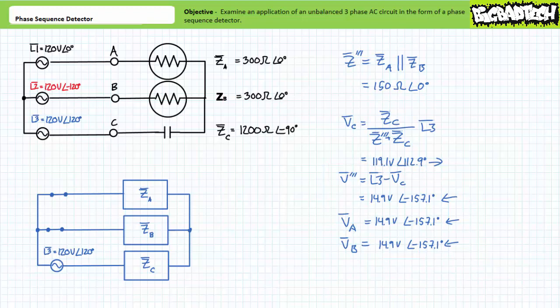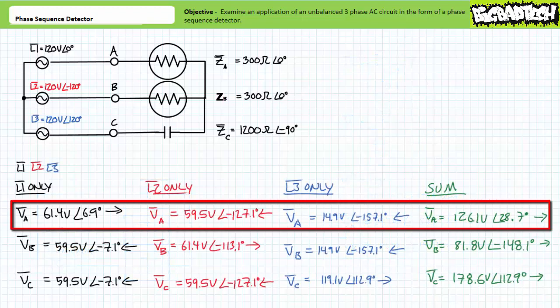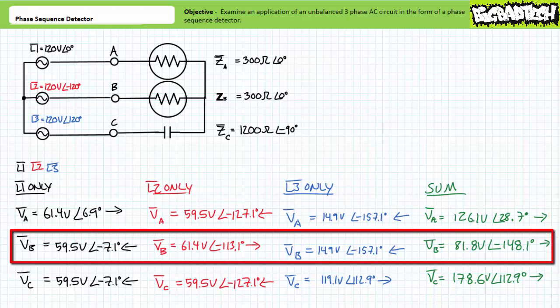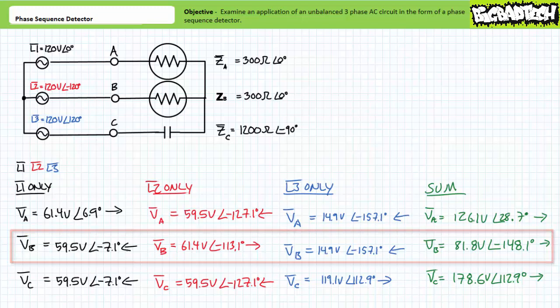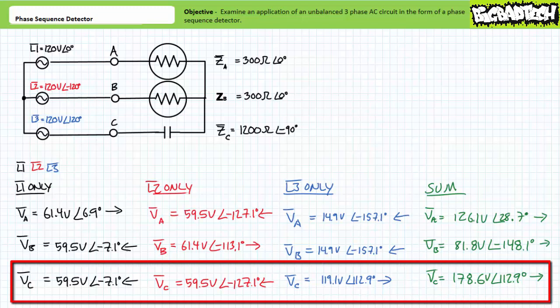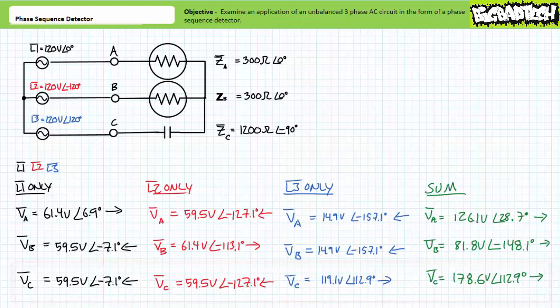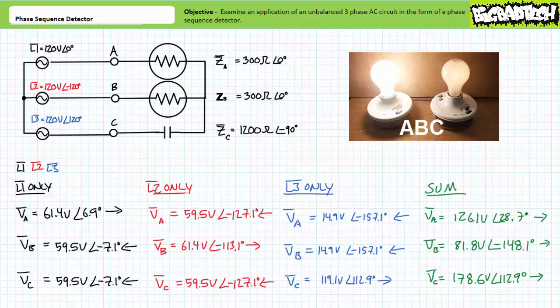Let's now sum the previous results. Accounting for magnitude, phase shift, and polarity, load impedance ZA experiences a voltage drop of 126.1 volts at an angle of 28.7 degrees, with assumed polarity positive to negative left to right. Similarly, load impedance ZB experiences a voltage drop of 81.8 volts at an angle of negative 148.1 degrees, with assumed polarity positive to negative left to right. Load impedance ZC experiences a voltage drop of 178.6 volts at an angle of 112.9 degrees. Given these voltage differentials, it should be obvious that light A would be brighter than light B — a clear indicator that the phase sequence is ABC and not BAC.